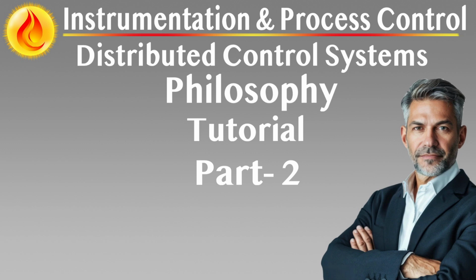Field implementation and safety devices, smart safety devices. All field devices connected to the ESD system, e.g., final control elements, sensors, shall be SIL rated, explosion proof, Ex d or Ex ia, and certified for Zone 1 or Zone 2 as applicable. Where possible, smart diagnostics and event memory are enabled.